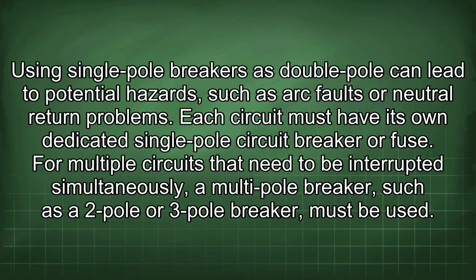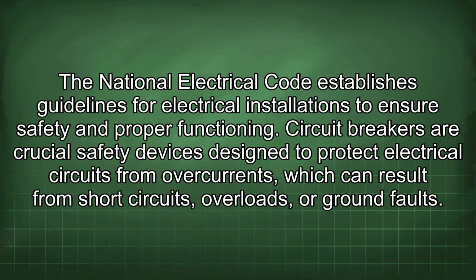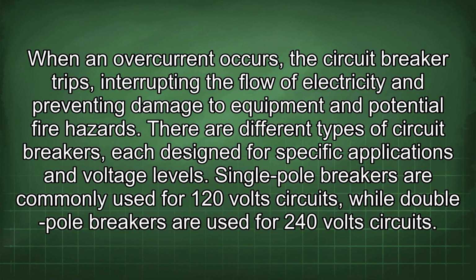For multiple circuits that need to be interrupted simultaneously, a multi-pole breaker such as a two-pole or three-pole breaker must be used. The National Electrical Code establishes guidelines for electrical installations to ensure safety and proper functioning. Circuit breakers are crucial safety devices designed to protect electrical circuits from overcurrents, which can result from short circuits, overloads, or ground faults. When an overcurrent occurs, the circuit breaker trips, interrupting the flow of electricity and preventing damage to equipment and potential fire hazards.